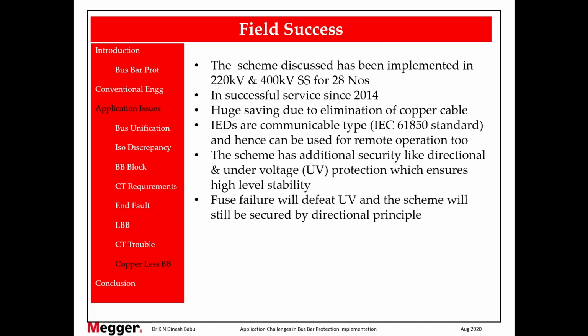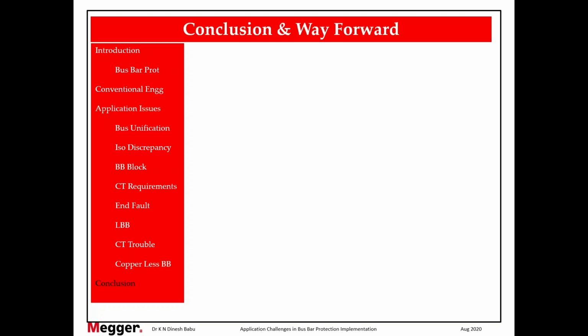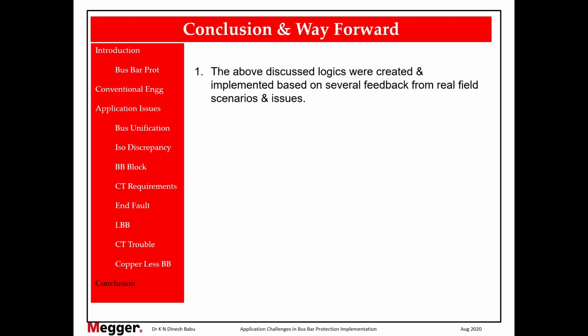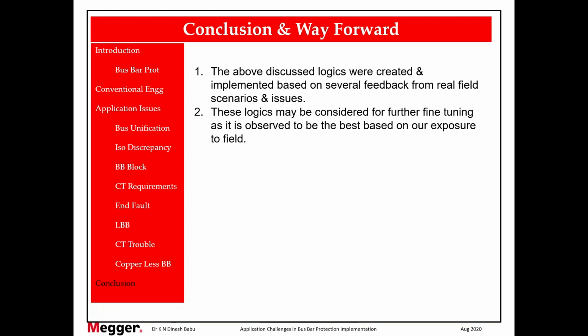And whenever there is a fuse failure, undervoltage will be permitting the tripping. Unlike distance protection where undervoltage will be blocking distance, here in the busbar, whenever the fuse fails, that particular input will become high. So it will wait for the main zone and check zone only. So that also is addressed here. So in conclusion, the logics which we have discussed are based on the real feedback given by users from time to time, based on all the fault analysis which we have been doing. So based on that, these logics were developed and installed.